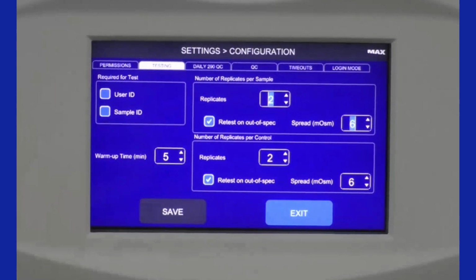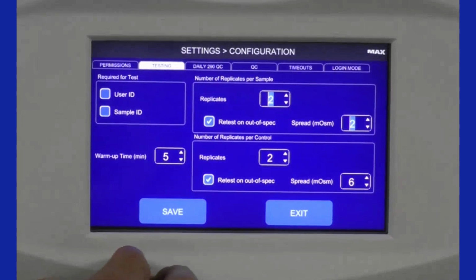But another cool thing is, let's say you set it at 2 replicates per sample, you can designate an acceptable spread between those 2 results. So let's say you don't want them to be more than 2 milliosmoles apart. You can designate that here, and then you can select that box on the left to automatically retest that sample if it's outside of the spec that you set for an acceptable range between those 2 samples. So pretty cool feature. And in that rectangle down below, same feature, except it's for your QC. So it's for your controls. So you can set a number of replicates per control that, again, your instrument will recognize based on the barcode in those ampule adapters. And it will automatically run however many replicates you set on each of the controls that you load into the turntable too, where you can also set that spread, depending on how you want it.